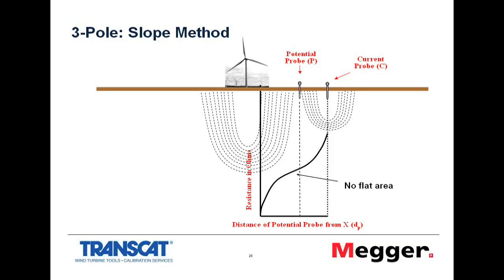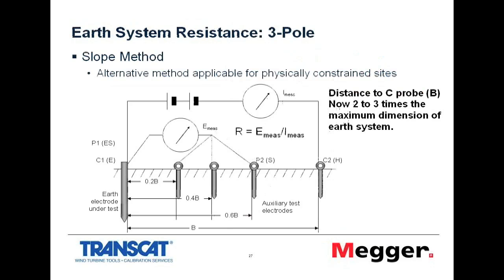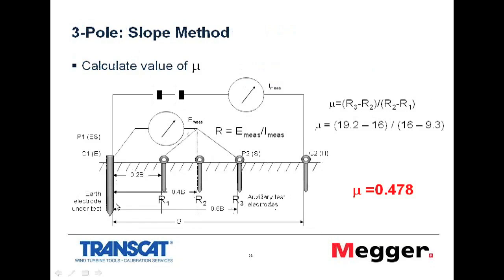Now, if there is no flat, as you can see here, I've shown a graph where I have no flat region. Then the next method I can use is called the slope method, because we don't have a flat area, we only have a slope. Now in this method, it does involve some mathematics, but it's not a difficult test to do. You do 3 measurements with the voltage probe or the potential probe at 20%, 40%, and 60% away from the earth system I'm measuring. I put those values into a formula. I won't run through that in detail because of time, but you get a value for mu.